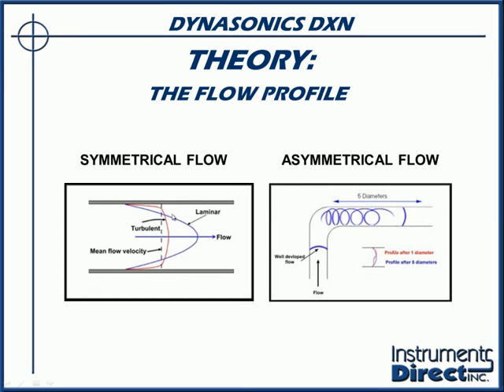That's not so much important, but what is important is, if you were to draw a center line down this pipe, the top half of flow equals the bottom half of flow, then you're really going to get an optimum performance with most flow meters. This situation normally occurs when you have enough straight run of pipe, traditionally 10 to 15 pipe diameters and flow rates of 10 feet per second.